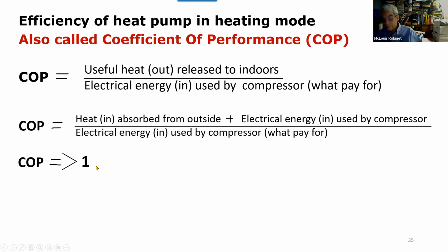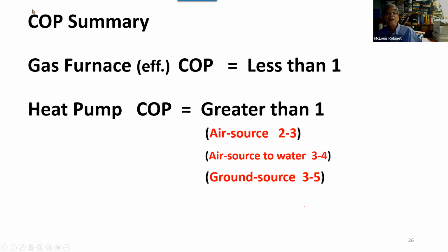So this is what it's all about. The coefficient of performance of a gas furnace is always some number less than 1. That will never change. The coefficient of performance of a heat pump is always greater than 1. If it's not greater than 1, it's not a heat pump. For air source heat pumps, the coefficient of performance is between 2 and 3.